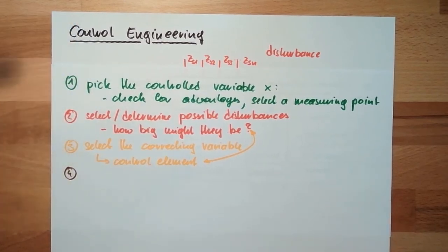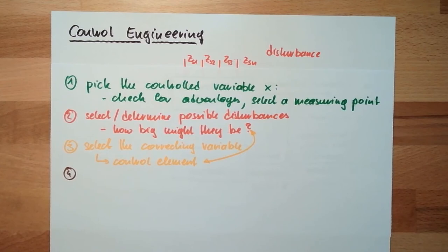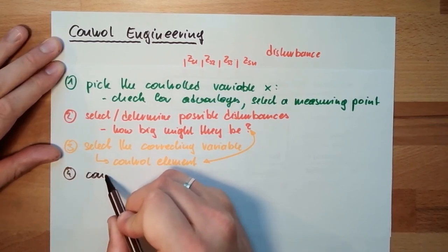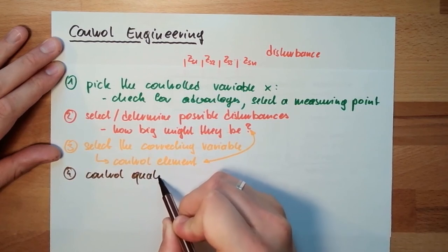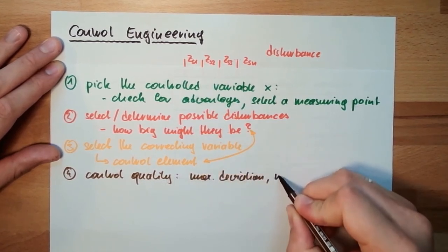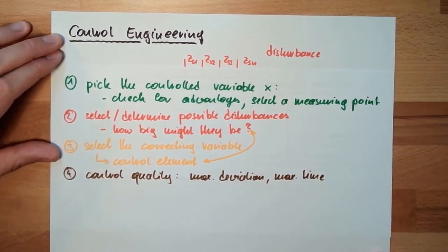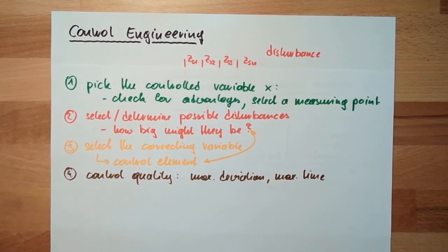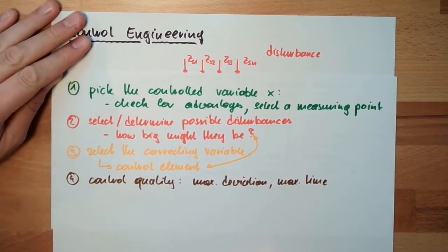Now we're talking about control quality — that's the fourth point. I need to know what quality means here: what is the possible maximum deviation, and how long do I have to bring the control variable and the reference variable together? I need to define maximum deviation and maximum time for reacting. If I set everything to zero, it becomes expensive — so there are tradeoffs to consider.